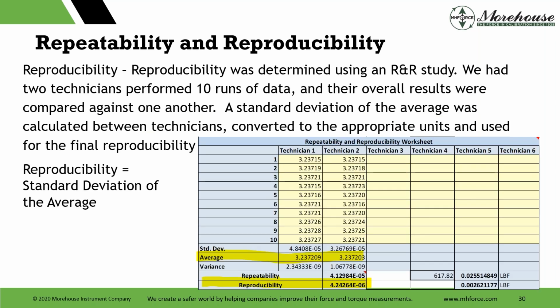So what we're generally going to do here, remember, we've taken that load cell, we've done repeatability, we've done it throughout our range. If it's a 2,000 pound load cell or 2,000 Newton or whatever units you want to work in, we want to do a point at least every 10% of that range. And now here we're saying, okay, let's find out, let's do different technicians. I only put 2 in this example here. So let's take different technicians and see what's going on with them.